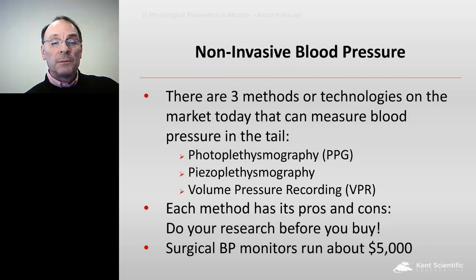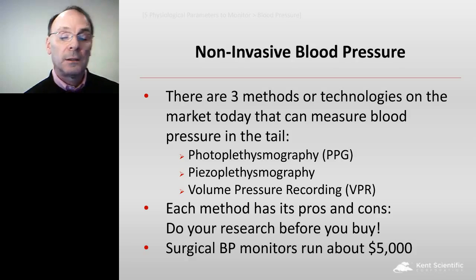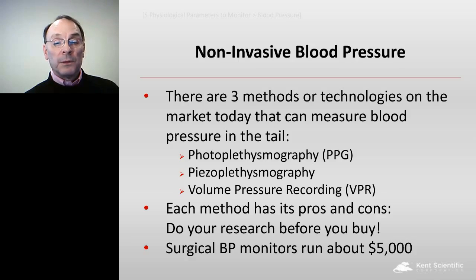There are different types of methods. The one that seems to be the oldest method is photoplethysmography. That's shining a light across the tail and trying to pick up the pulsations on the other side of the tail with a photosensor. People have used a piezo sensor or a strain gauge around the tail, called piezoplethysmography. And the last one is the volume pressure recording technique. That is used with an additional sensing cuff on the tail to get accurate readings from the tail. The VPR cuff is actually pressurized and squeezes the blood out of the tail. And then when the blood flows back into the tail, the method mechanically integrates the blood coming in and gives accurate readings of systolic and diastolic pressure.